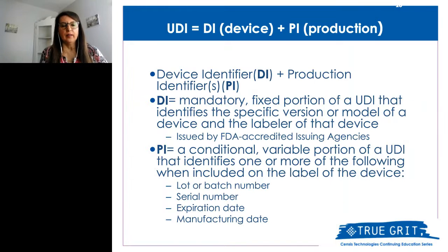So what is the UDI? If we look at it, it's really 2 pieces of the puzzle. One is the device identifier. That's going to be like the catalog number. That's the part that doesn't change. It's always going to be part number 1, 2, 3, 4. What's going to change is the production information. So if there's a lot number, a serial number, or an expiration date, that is what is going to change. So the DI is static, the PI is what changes.